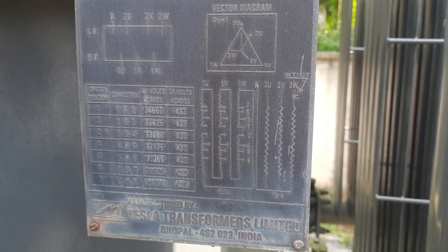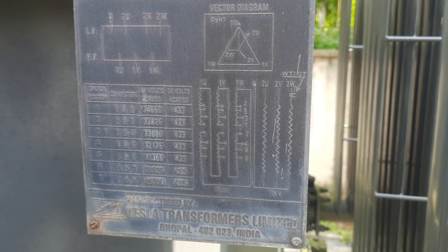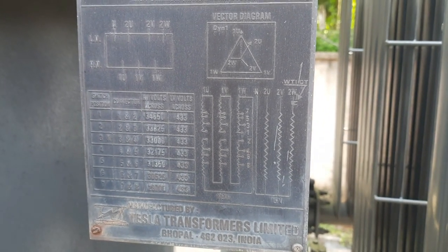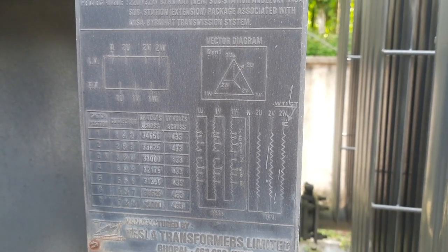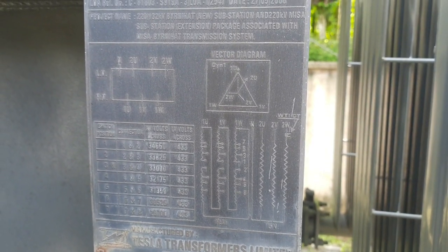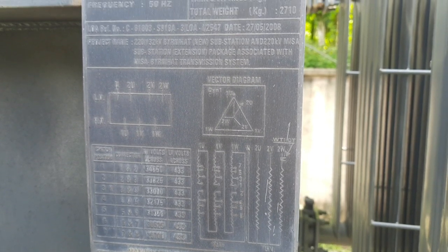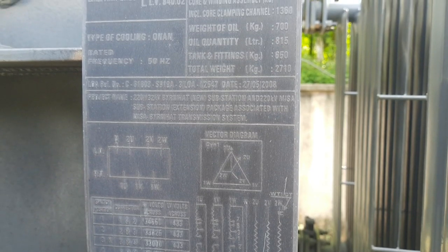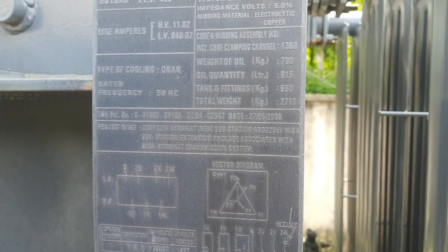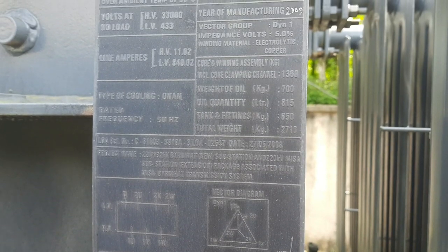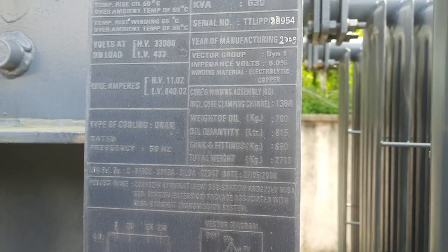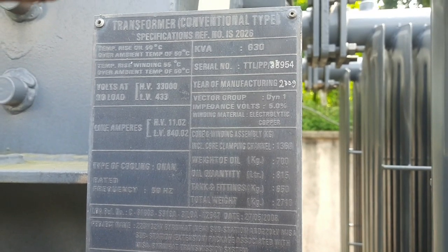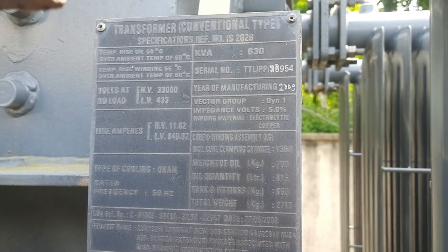And this is the phasor diagram, the vector diagram I have already discussed, and this is the connection. The windings have been given like this, as you can see. There is no physical connection between the high voltage and the low voltage windings. It's written there 1U means your high voltage winding and 2U is the secondary winding. Sometimes you will see 3 also in some cases. That means you have a tertiary winding in that case. So this is what you see about this transformer, which is a distribution transformer, all right.